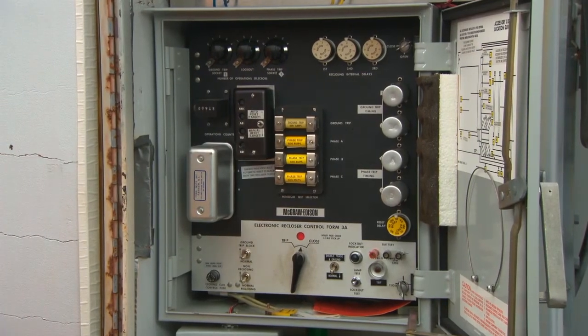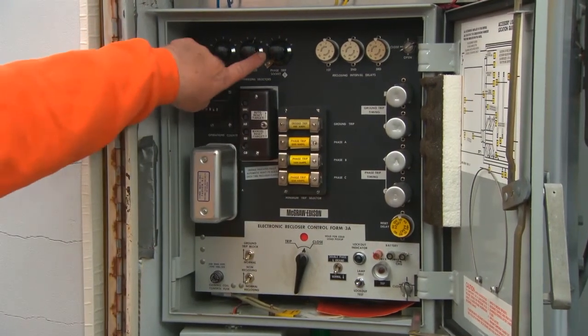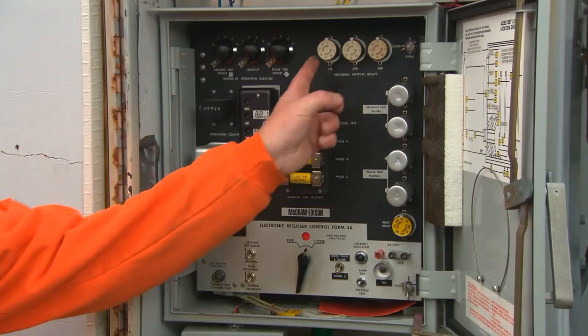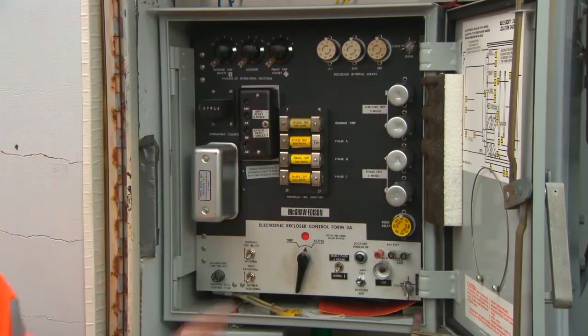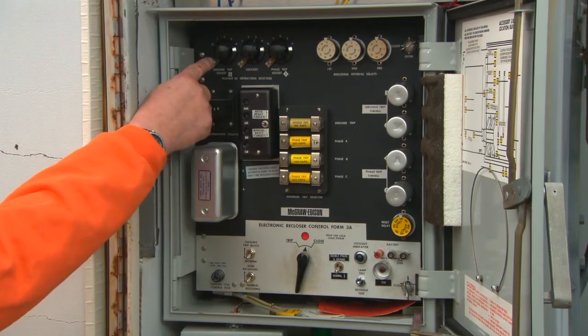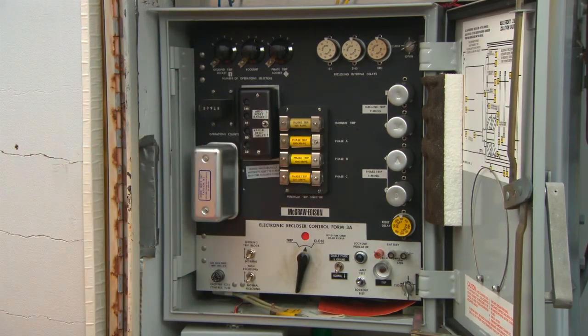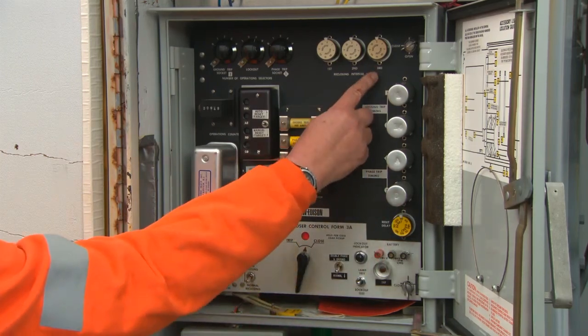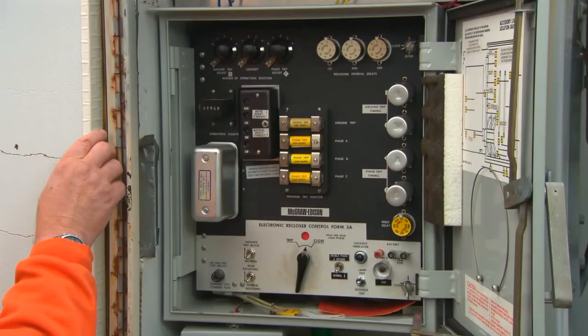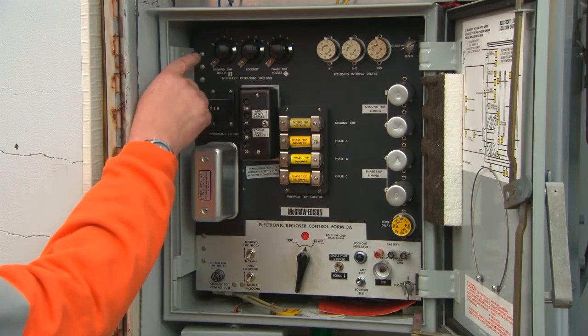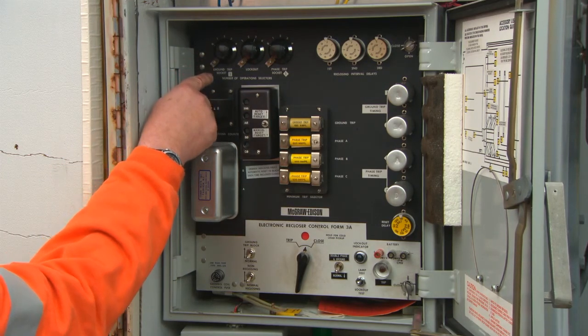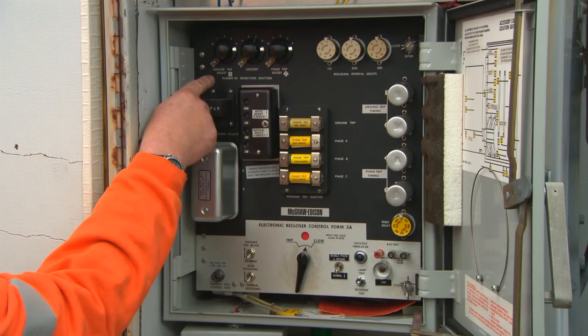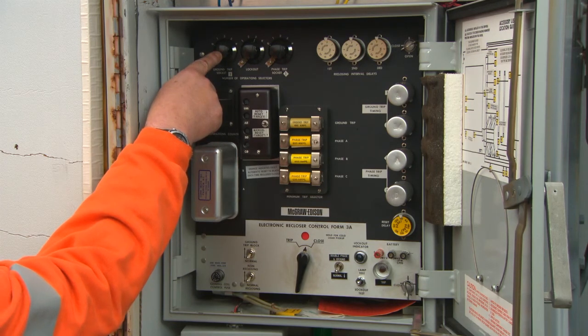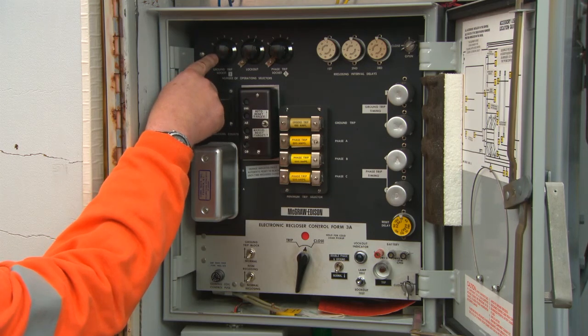Across the top of the unit are the operation selectors for the ground trip socket, the lockout socket, and the phase trip socket. The phase trip socket 1 will be set to your fast operation. In this particular unit, the selector is set to 0. The ground trip socket 1 selector is used to select the number of fast ground trip operations as defined by the timing plug in socket 1. The remaining slower operations are defined by the plug in ground trip socket 2.